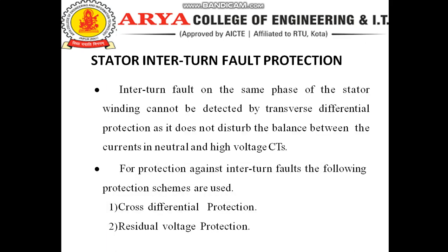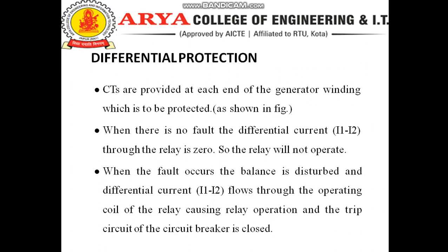Now we discuss the stator interturn fault. An interturn fault on the same phase of the stator winding cannot be detected by transverse differential protection, as it does not disturb the balance between the currents in the neutral and high voltage CTs. For protection against interturn faults, the following protection schemes are used: the first one is cross differential protection, and the second one is residual voltage protection.